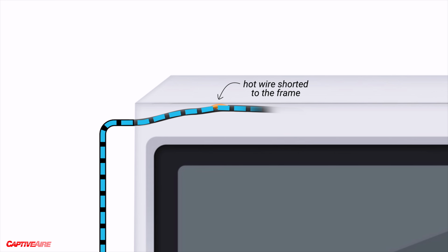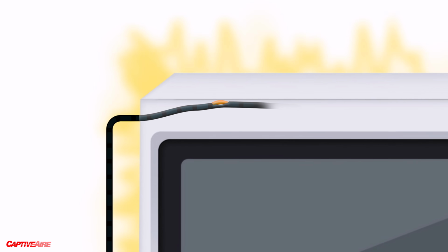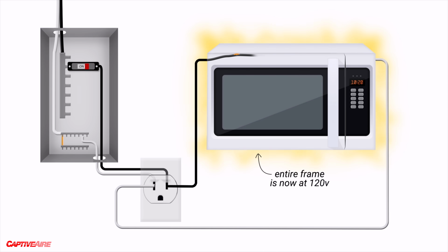We would say here that the wire is shorted to the frame, and this would be a very dangerous situation, as the frame would be at 120 volts of potential. That's a bit like leaving an exposed cable that someone is very likely to touch and get shocked.